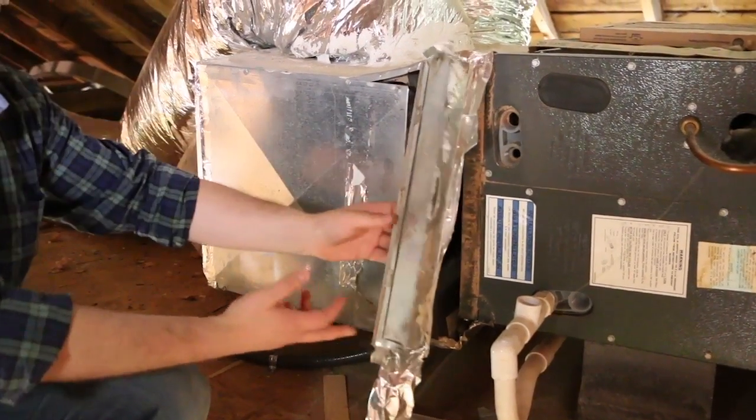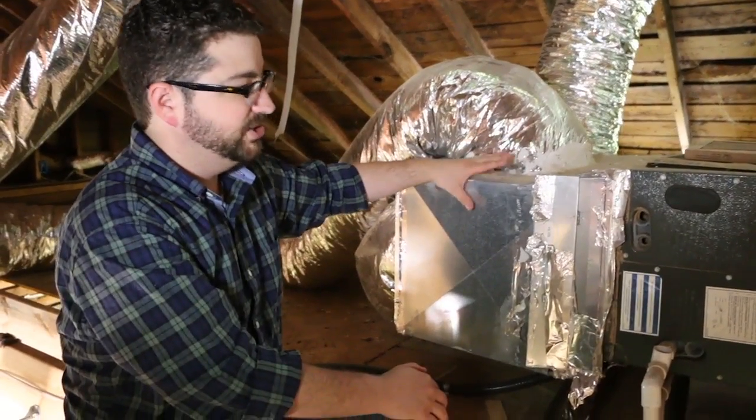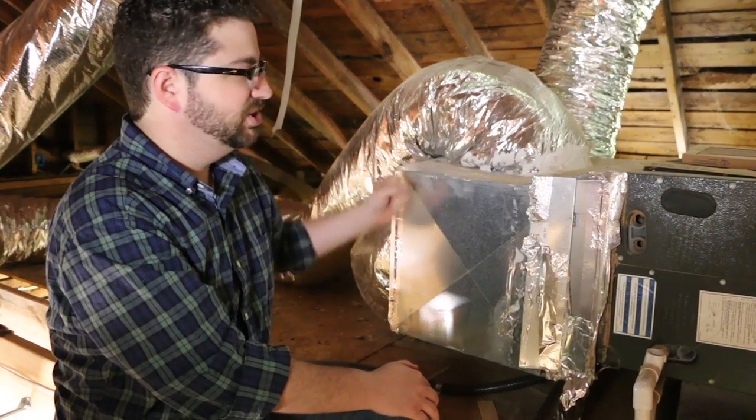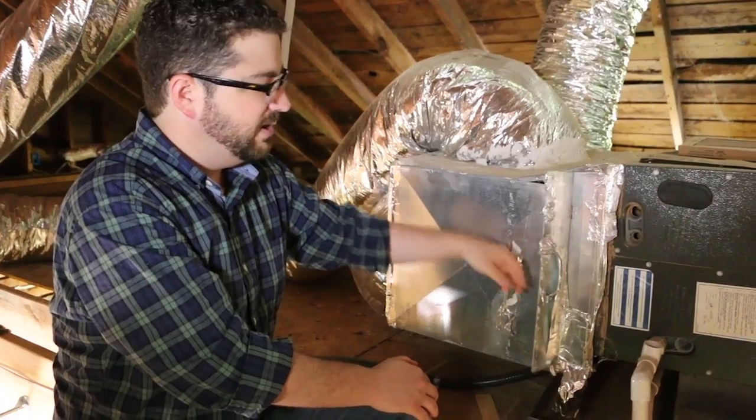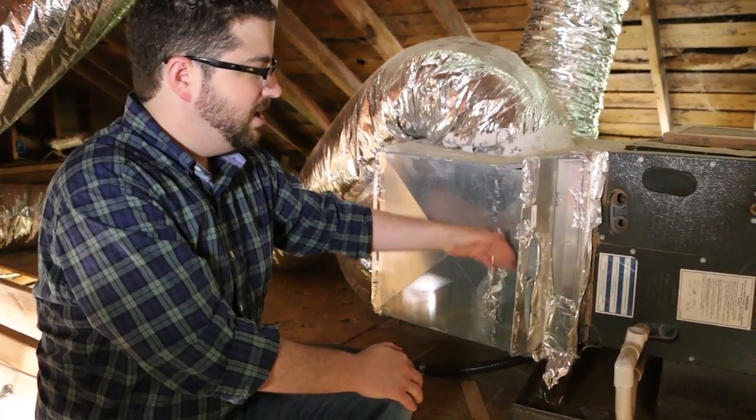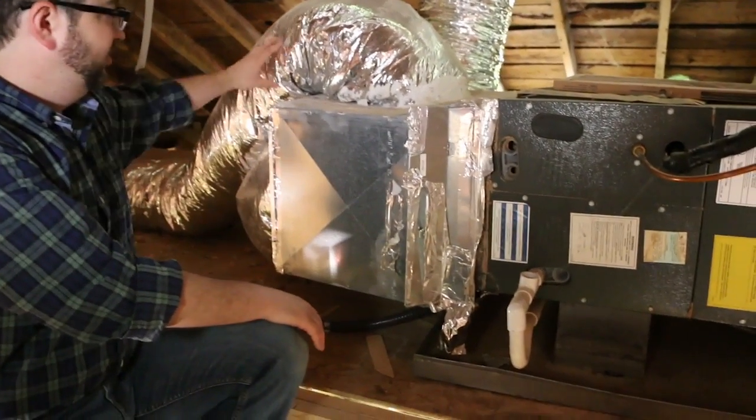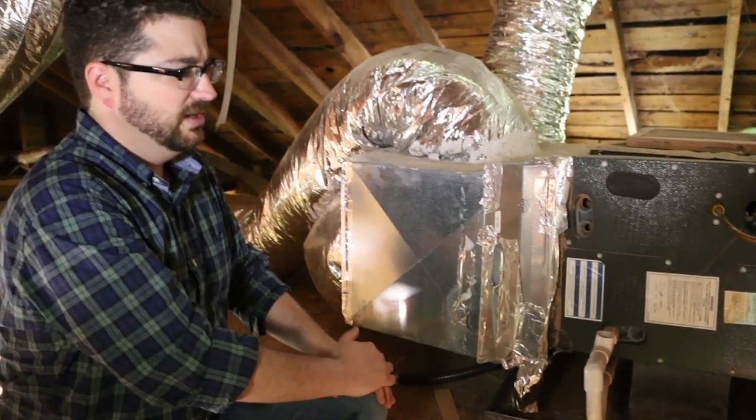The irony of this is right here is where the air pressure in the system is the most negative, meaning the suction is the greatest. So if this system were running right now, the majority of the air would just be sucked in right through here, and the return ducts are going to do very little, if anything.